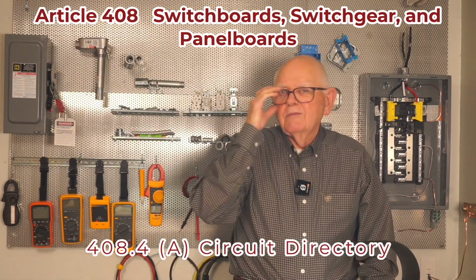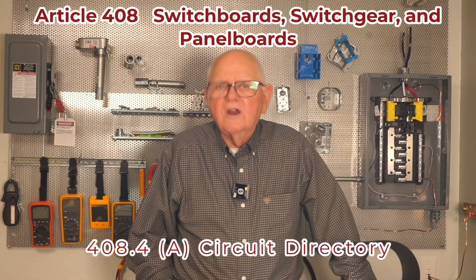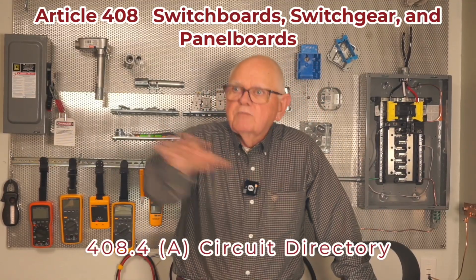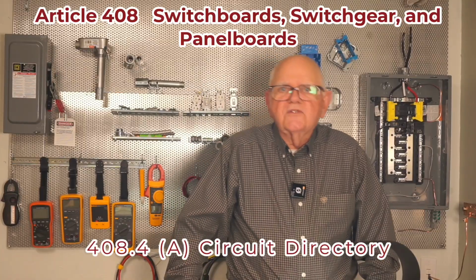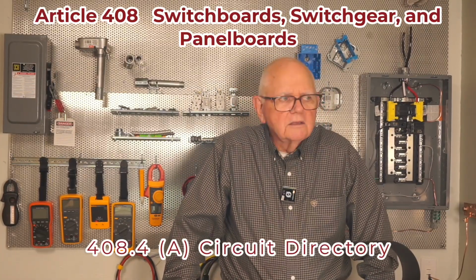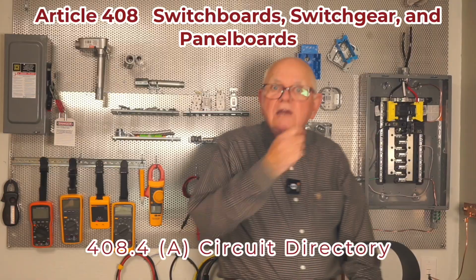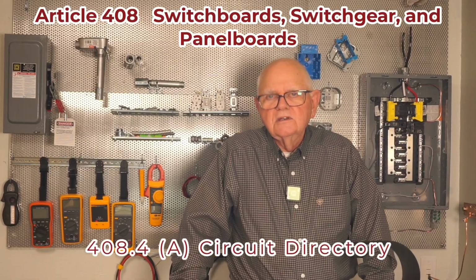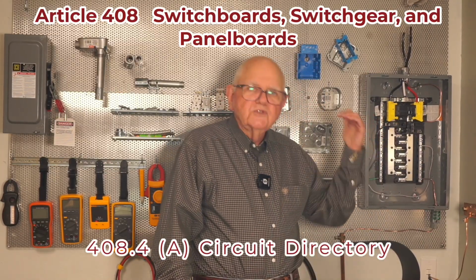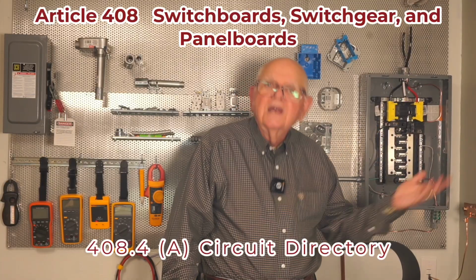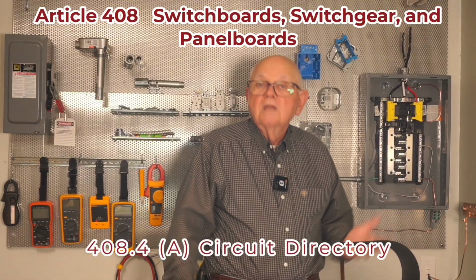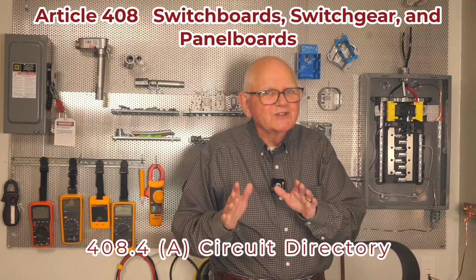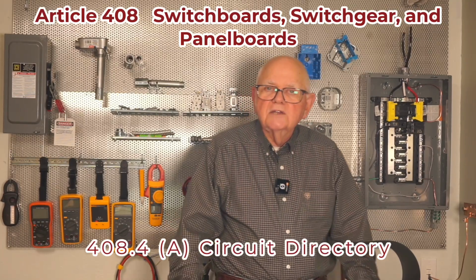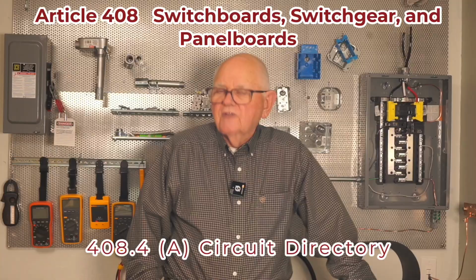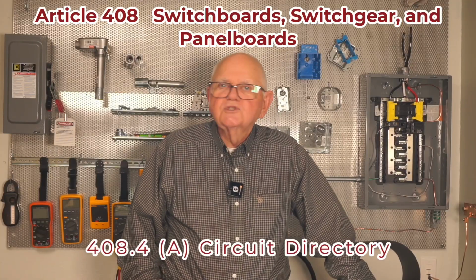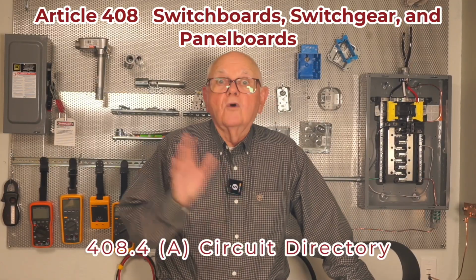The other is, and maybe more typically what we would use it for, lockout, tagout. I need to replace a couple of those receptacles on the south wall. Oh, I wonder what breaker it is. Well, let's keep trying until we get the right one. That's no good. It needs to be clearly marked: room 201, receptacle, south wall. Now I know what I'm doing, right? I'm still going to follow all my requirements and verify the circuit's de-energized, but nonetheless I can do a much more effective job in my lockout tagout process. So circuit directories are very important to us for safety.